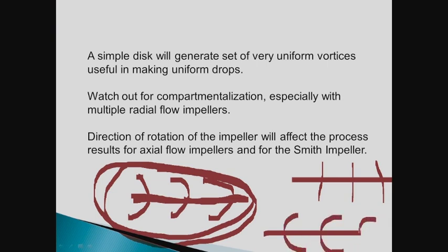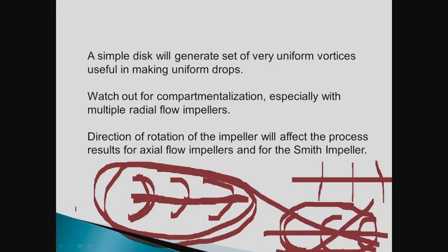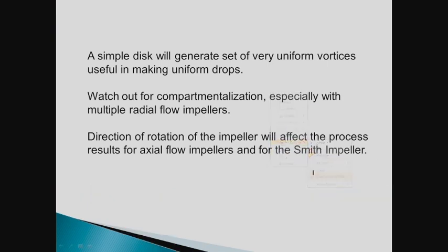Now, this is a disaster for gas dispersion, right? You want it cupped in the direction of rotation. So what happened was these guys in the maintenance flipped the impeller, or they basically wound up putting this thing in. And this is a disaster. Anyway, is that okay? Was that socially correct? I'm not sure. Who cares? Anyway.